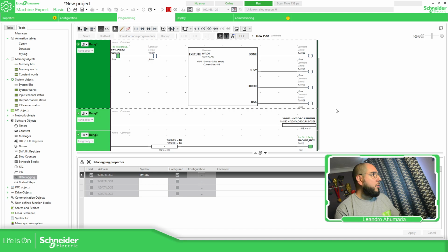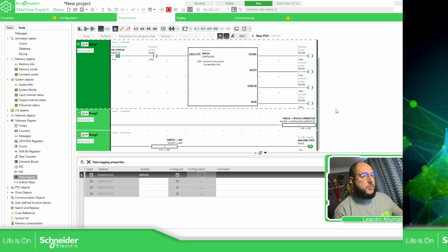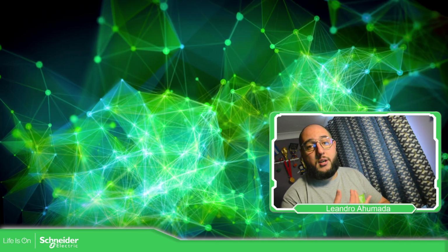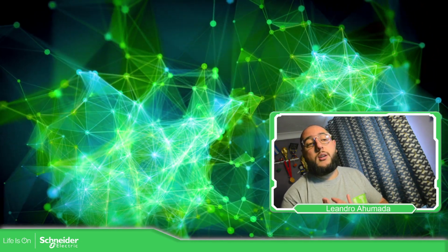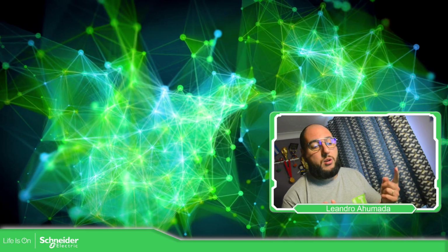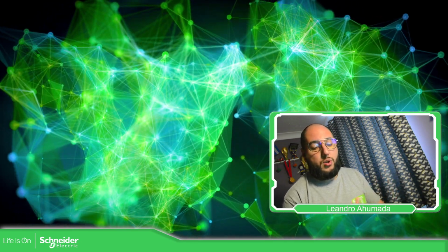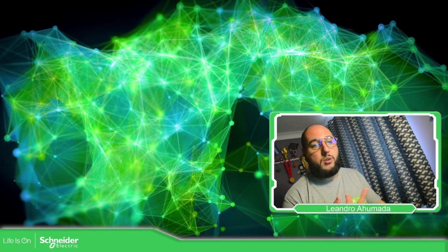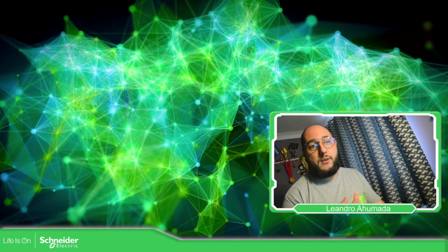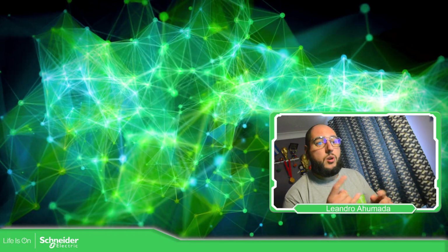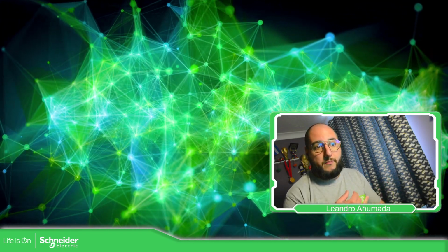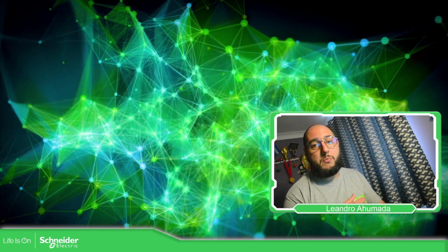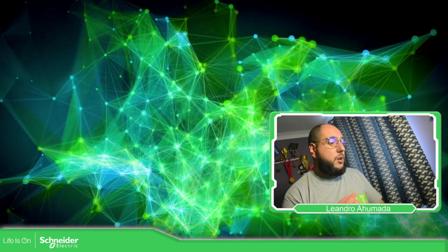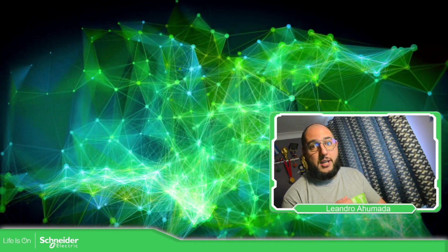Okay, so I believe this is it for the SD card logging on the M221. It's very simple, very straightforward. Just need to know which is the function block to use, which are the variables that you want to use, and when and how to trigger it. Okay, and it's important to know the SW7 bit 2 is the one that gives you the presence of the SD card. So the SD card also needs to have the data in there.